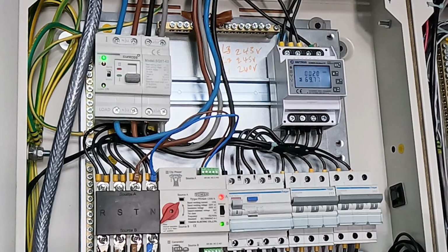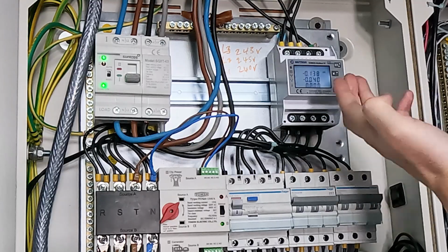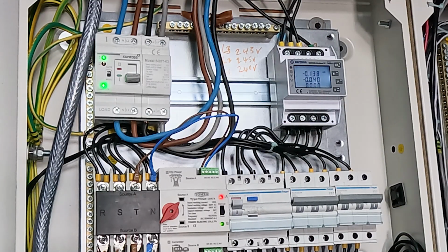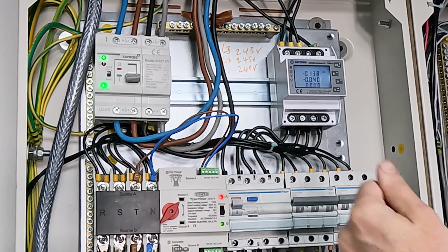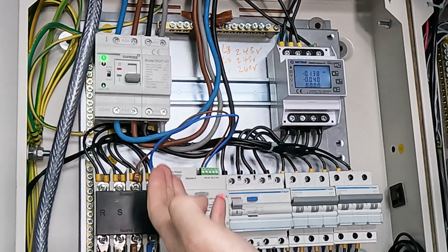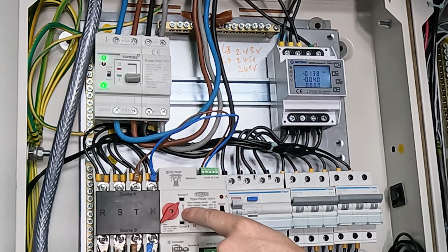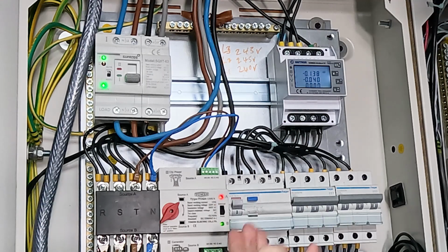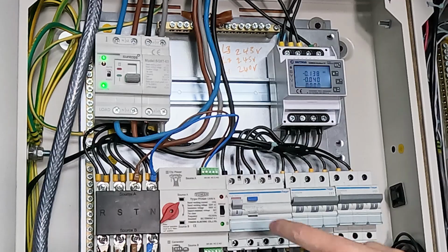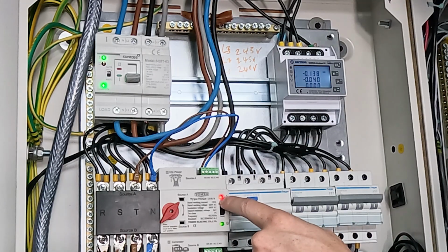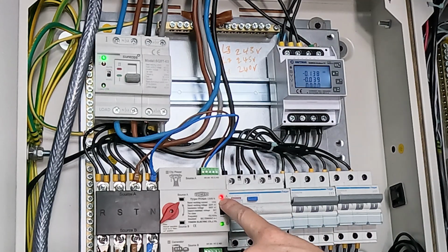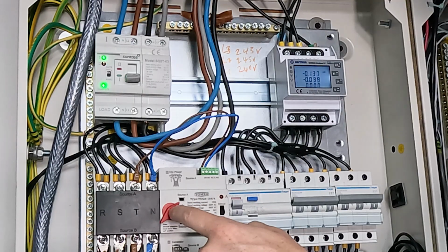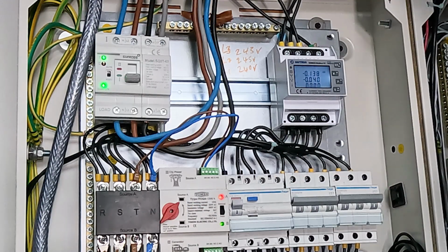And just to do some demonstrations, this is pointing to when there's power on my backup. And if I trip the grid, we would expect it to just remain on source A because my inverters are outputting voltage. These are also very good indicators that there's power on my circuit, and you can see here that I've got power on my source A, which is my inverters, and we would expect this ATS to just stay in its state because the inverters are outputting the voltage. So I'm just going to simulate that.